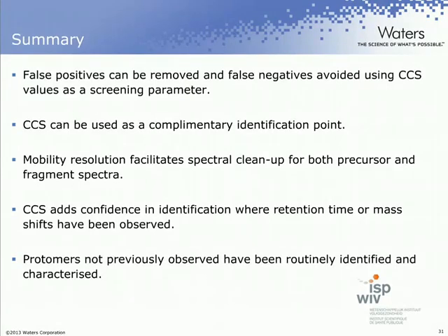We now have time for a few questions, and our first question, Mike, is, for ion mobility, how easy is it to set up, calibrate and configure my system so I can generate this extra dimension of data in my world? Well, the short answer to that, David, is it's easy to set up, it's routine, but just let me explain a little more. To perform ion mobility separation and acquisitions, all system parameters are default and can be used with confidence, so it's only a case of selecting ion mobility mode when using the SYNAPT system. Otherwise, it operates just like a normal QTOF.